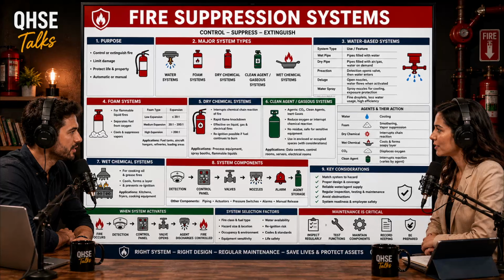That evaluation is the core essence of fire protection engineering. For the server room, the business continuity risk is massive. Water damage would destroy the servers. So your primary defense should be a total flooding clean agent system, like Novec 1230. It puts the fire out in seconds, leaves zero residue, and is totally safe for the IT staff.